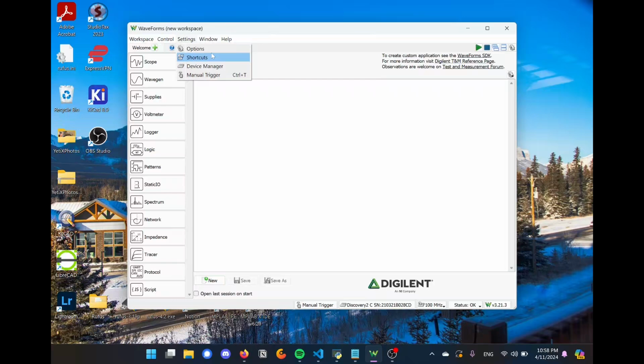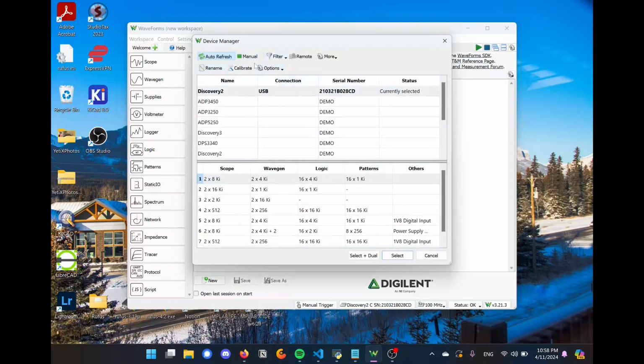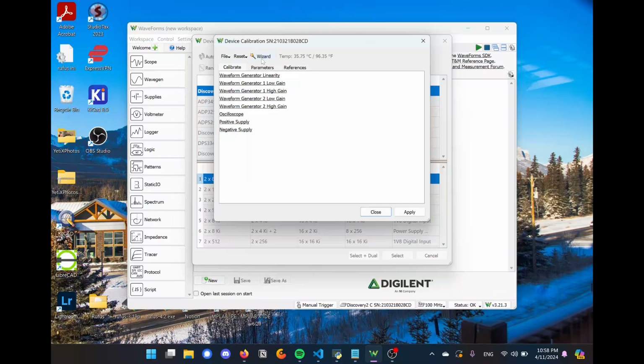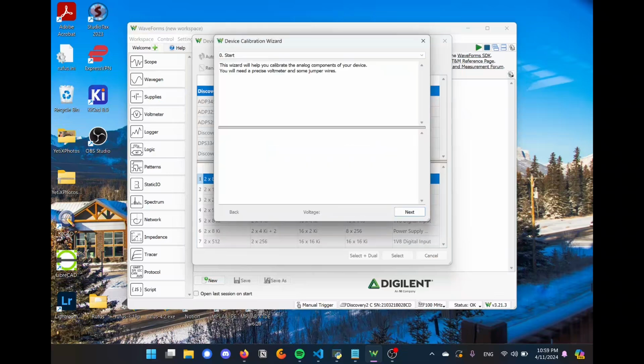This'll save me hours. Part of the reason that the Analog Discovery 2 is so difficult and time-consuming to calibrate is the many steps that are required. First, I have to open up the calibration wizard and do my linearity calibration. Next, I have 20 different voltages that I need to measure with a multimeter and enter into the software. 0.0021. 1.056. If I were to go through all of these, it would take a lot of time. I think you get the point.